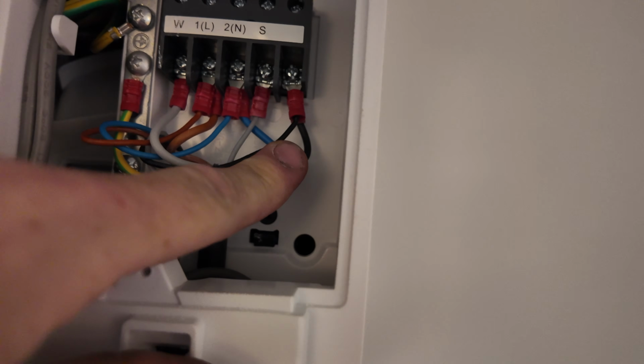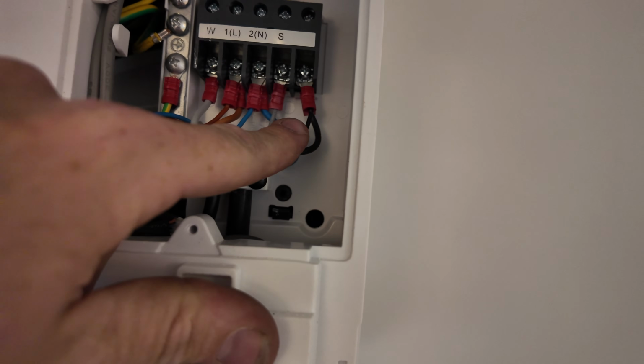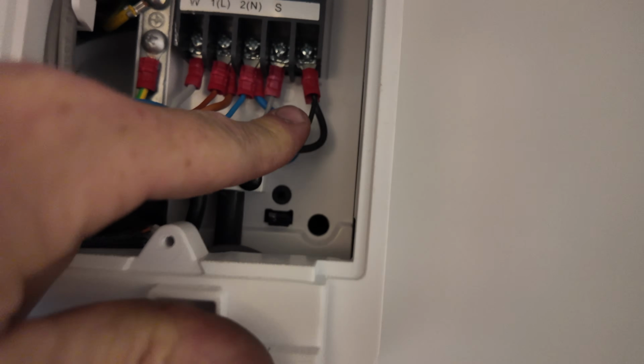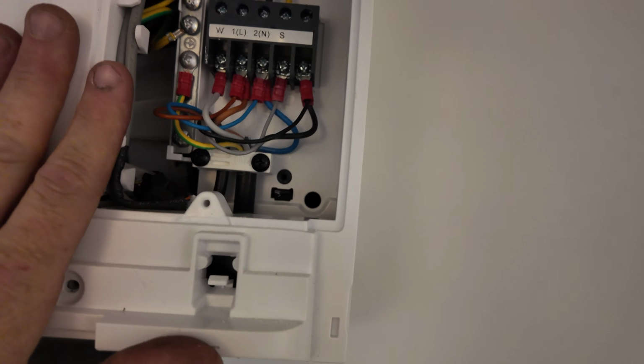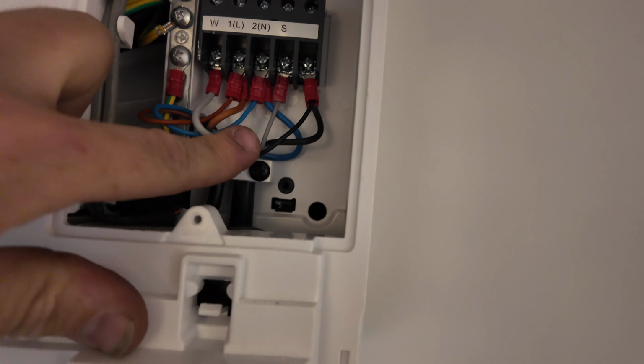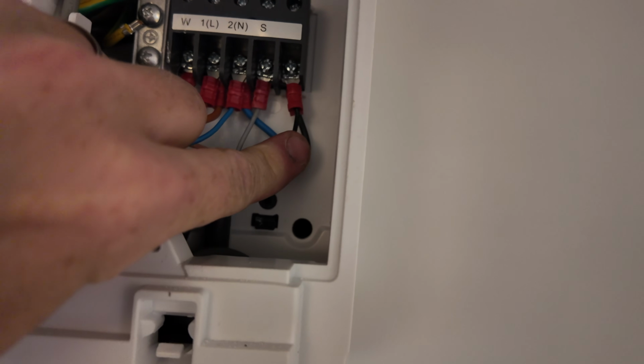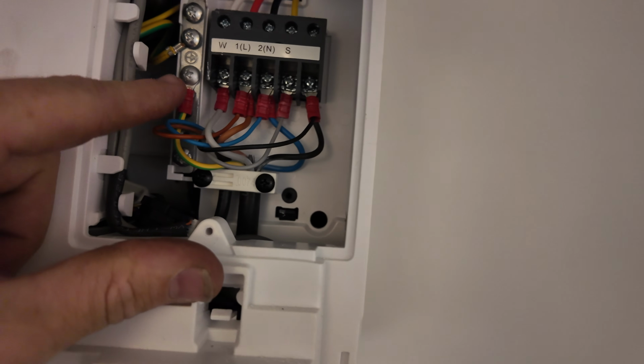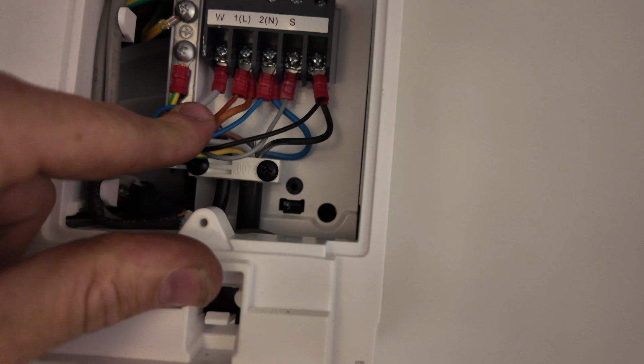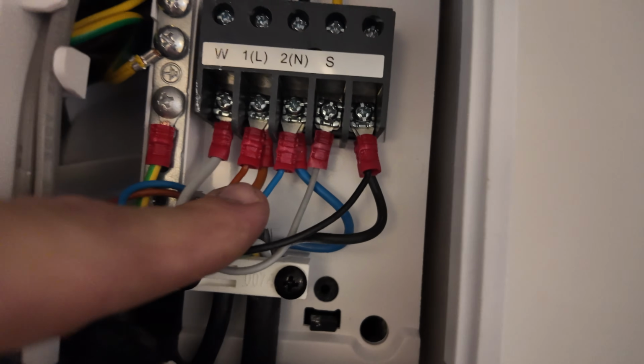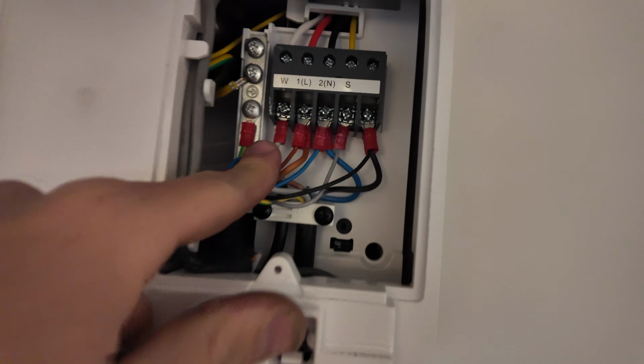You can see one of the smaller wires here is actually connected to the condensate pump, because we've got it linked here. That's your dead switch. So if your condensate pump fails, it'll stop the unit. It's going to cut the unit off here because it's got to go through the condensate pump first before it goes back through. I'll have to do a diagram just to explain that, because it might be a little bit fiddly, but that's how you wire up them pumps like that.